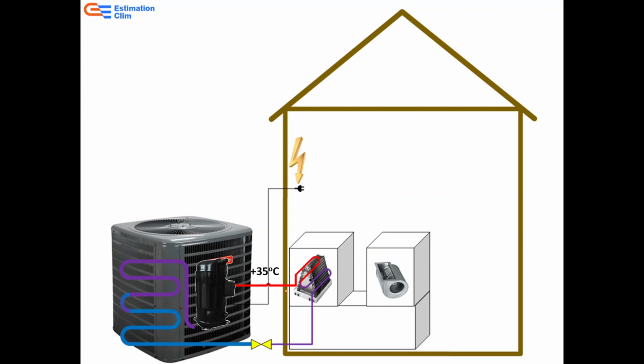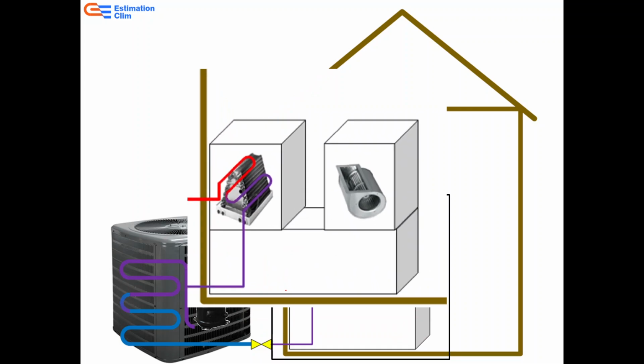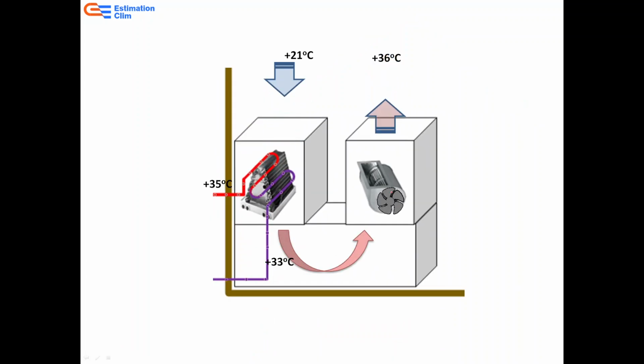Alright, let's see what's happening inside the air handling unit, which has a fan to circulate the air, an electric or gas furnace, and the heat pump heat exchanger, which in this case is acting as a condenser. We have plus 21 degrees Celsius return air coming from the return ducts. While it's going through the coils, which are at plus 35 degrees Celsius, it is getting heated and its temperature increases from plus 21 to plus 36 degrees Celsius. Finally, it's blown to the supply ducts and pushed back into the rooms. The internal working fluid is converting from gas to liquid phase, and by the time it's leaving the heat exchanger, it is a liquid at plus 33 degrees Celsius.